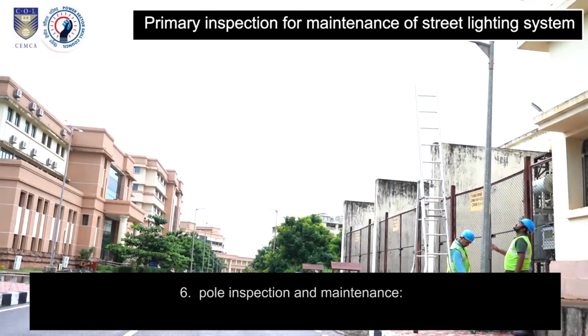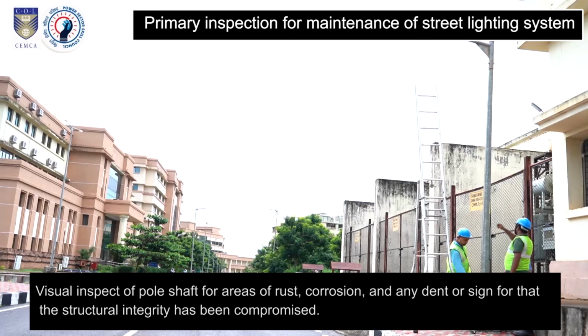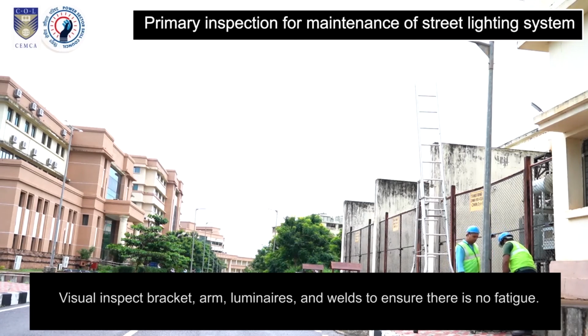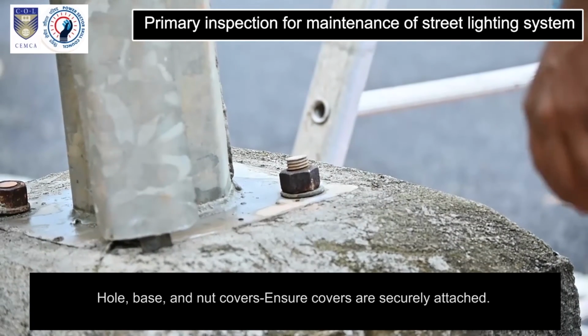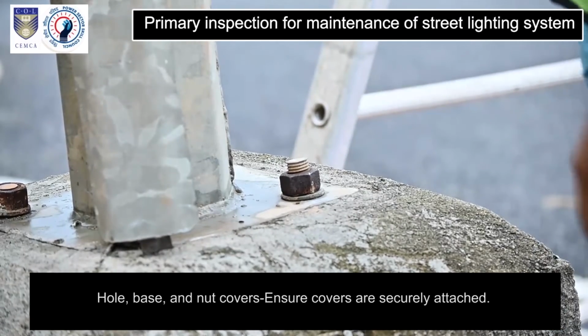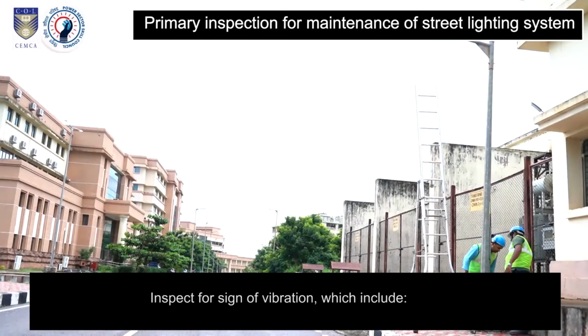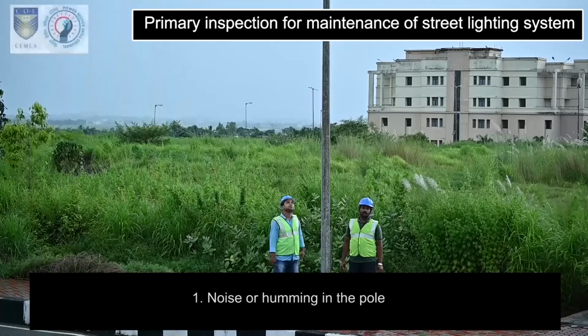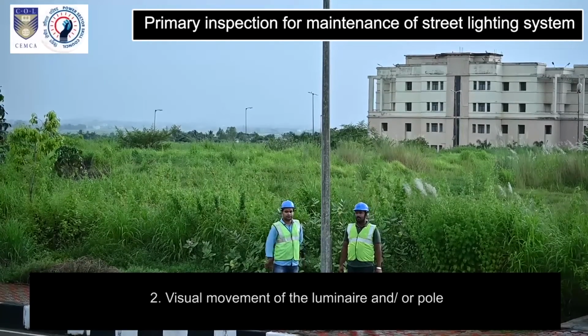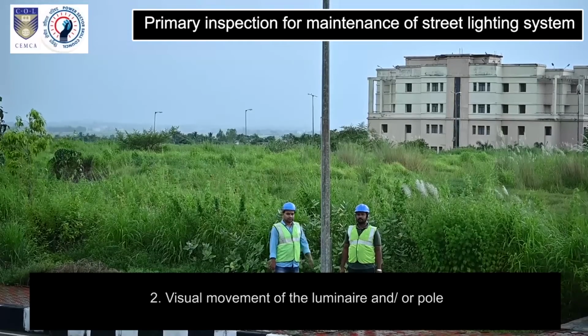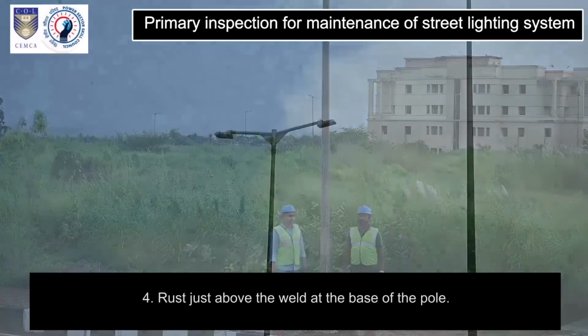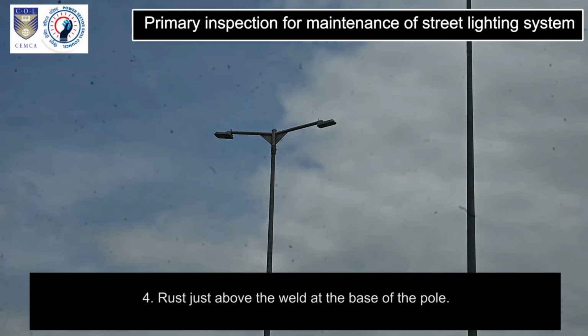6. Pole inspection and maintenance. Visually inspect a pole shaft for areas of rust, corrosion, and any dent or sign that the structural integrity has been compromised. Visually inspect bracket, arm, luminaires, and welds to ensure there is no fatigue. Hole, base, and nut covers: ensure covers are securely attached. Inspect for signs of vibration, which include 1. Noise or humming in the pole. 2. Visual movement of the luminaire and or pole. 3. Loosening of attachments. 4. Rust just above the weld at the base of the pole.